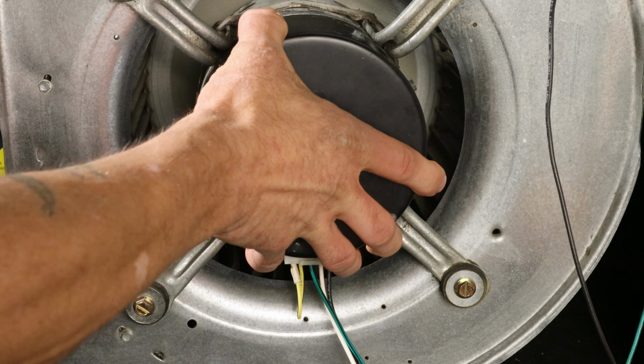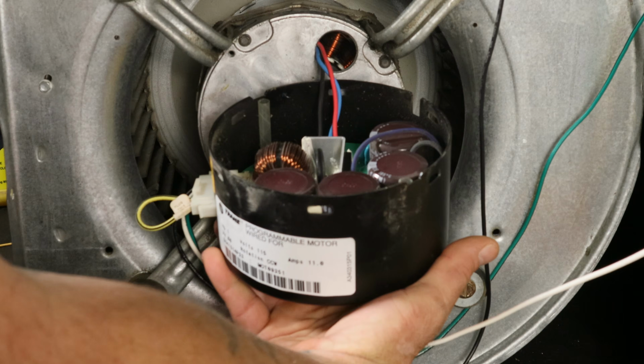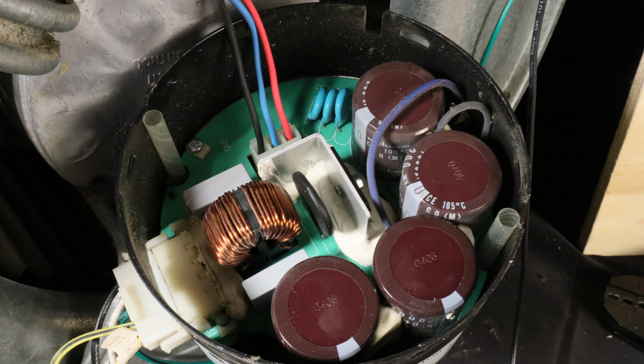And our module should come right off. So what we're looking at here is our connector block. This brings in the 120 volts and the communication signals. Next, it'll go to this black disc here, and that is a thermistor. So this is a surge limiter. When this is cold, it has a higher resistance value.